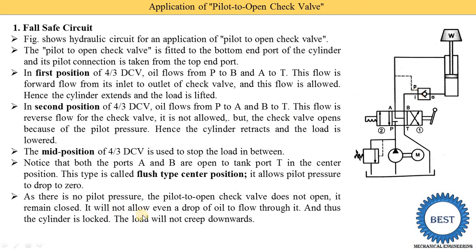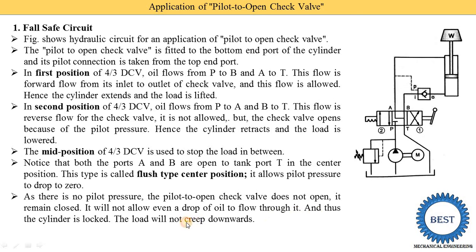The pilot-to-open check valve will not allow even a drop of oil to flow through it. Thus the cylinder is locked and the load will not creep down.